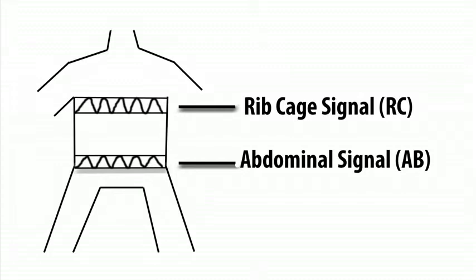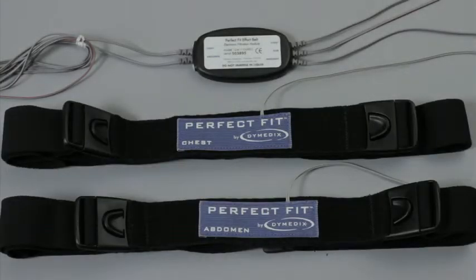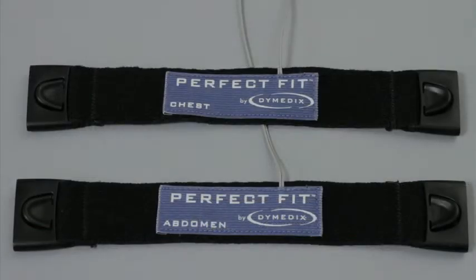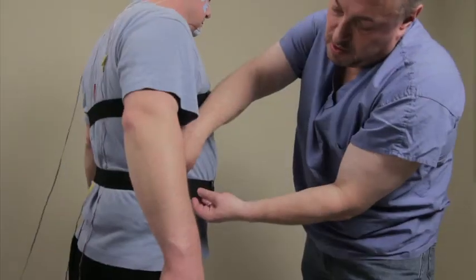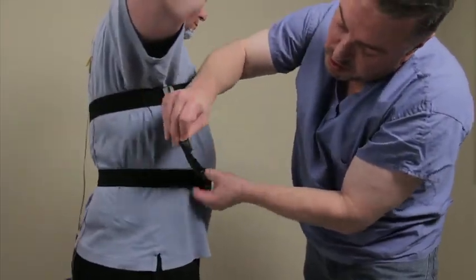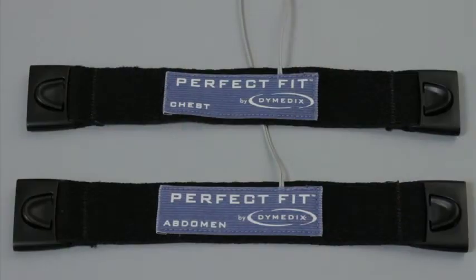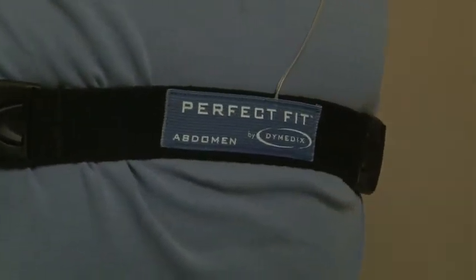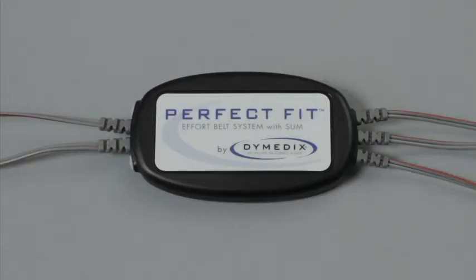Piezo crystal and piezo ceramic belts are no longer acceptable because they can show a false positive for paradoxical breathing. A recently completed 50-patient study found the perfect fit belts to be equivalent to RIP as it is commonly used. With low-profile, quick-release buckles for greater patient comfort, the perfect fit belts were designed to stay in place and be easy to adjust. PVDF shows true paradoxical breathing, and even when flipped completely over, they will not change polarity. When used in conjunction with the Dymedix airflow sensors, the signals will sync up perfectly. This is the great benefit of identical response times.